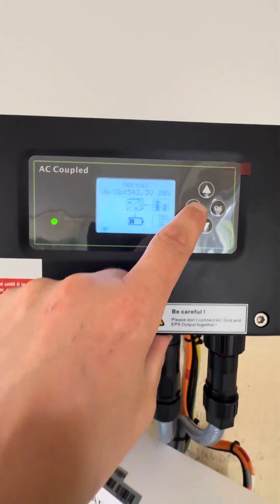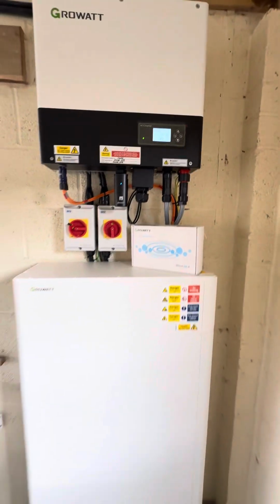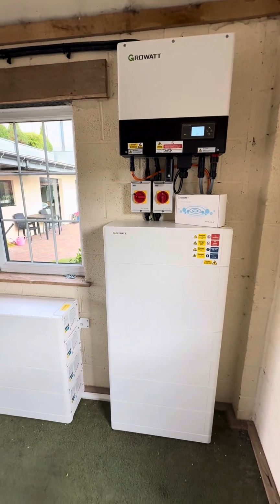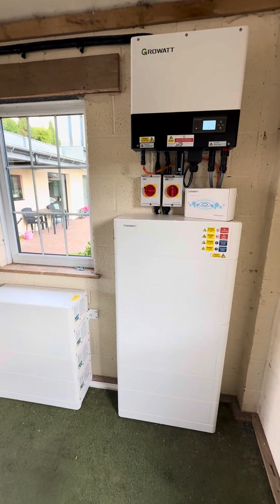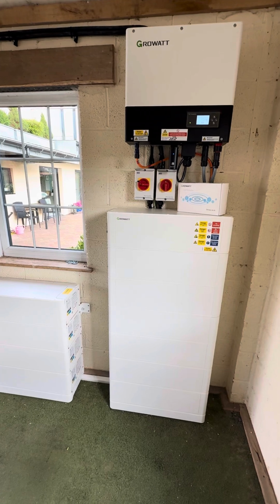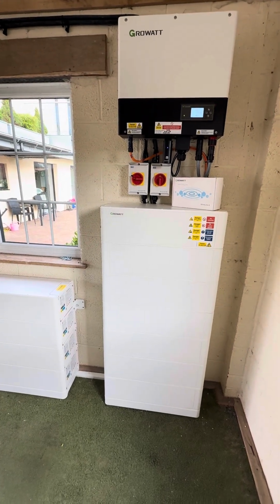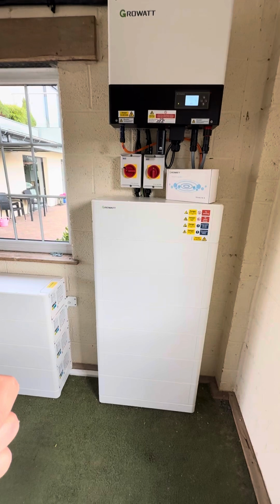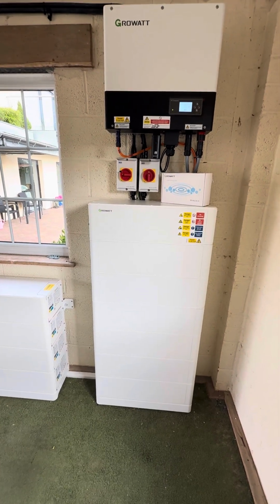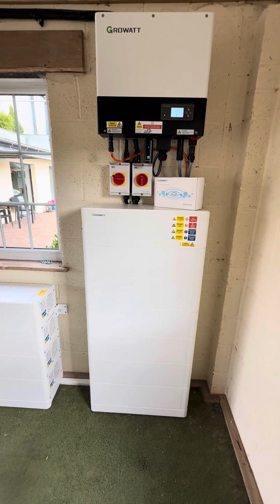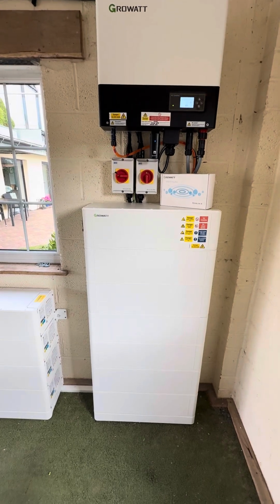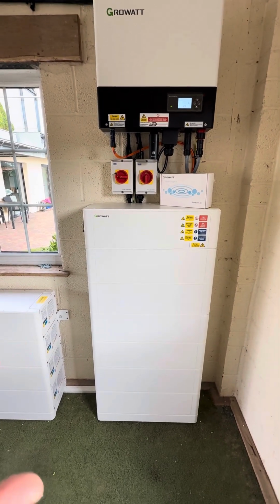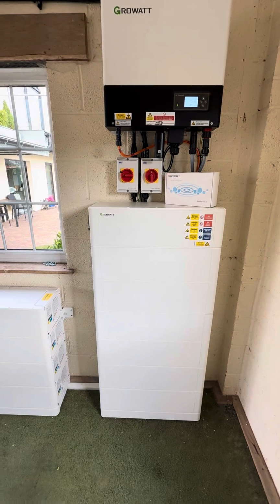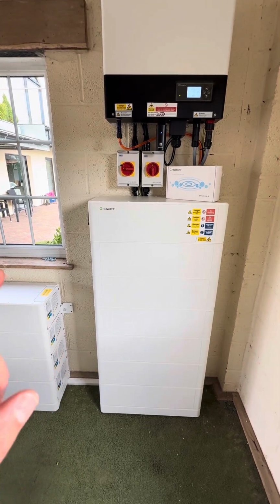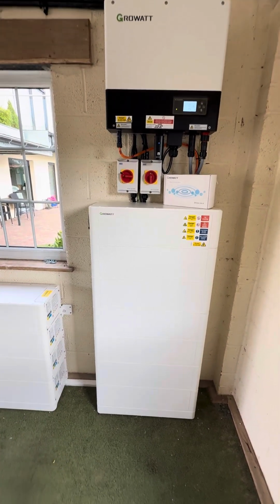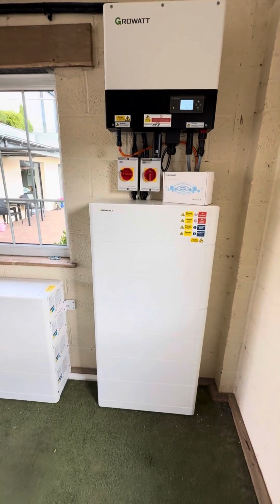This inverter will automatically differentiate information from an energy meter installed on the main incoming supply. That meter communicates with the inverter, telling it how much excess solar generation there is throughout the building and what the load consumption of the property is. It then works out the difference between the two, diverting the excess into the batteries, filling them up on surplus solar generation.